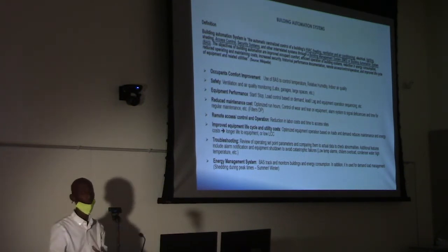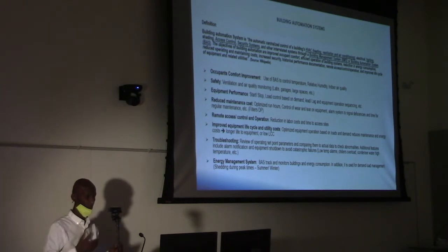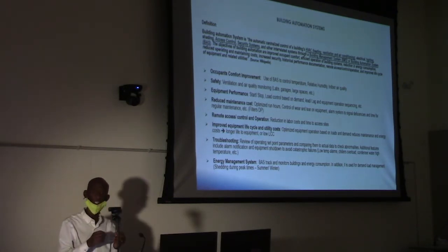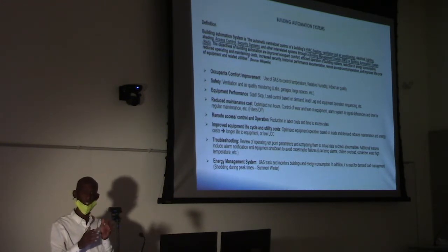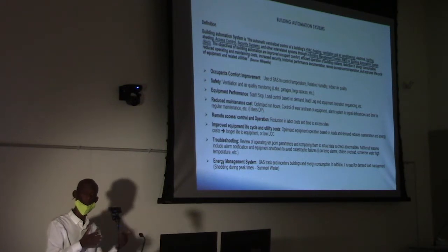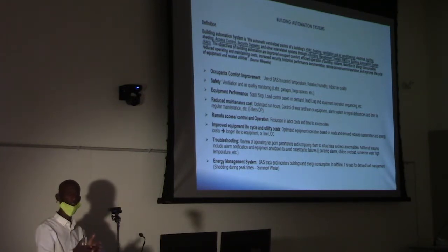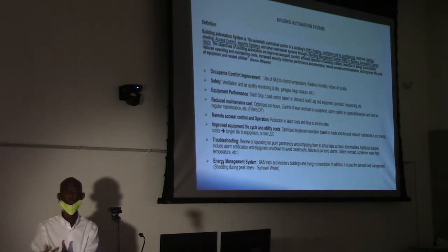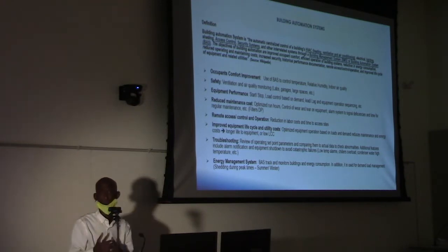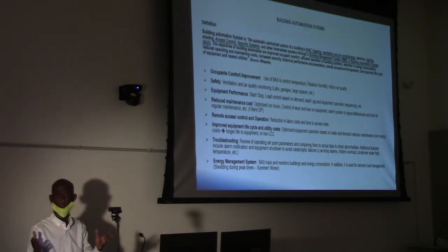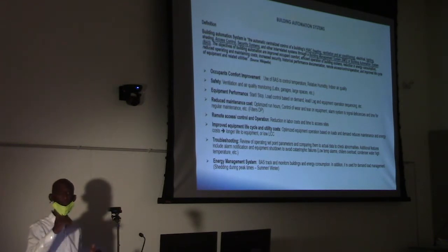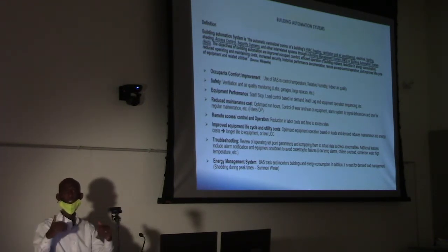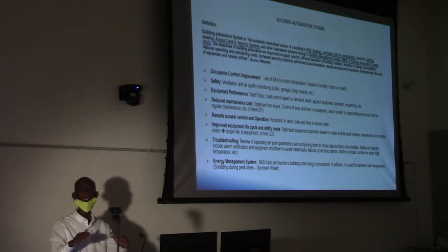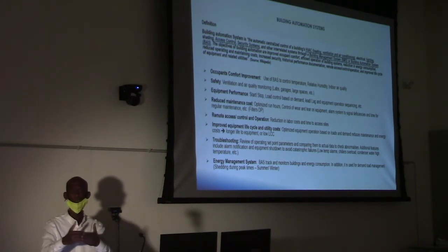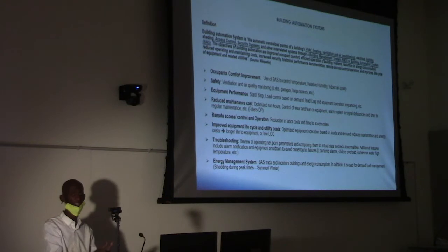So our building automation system has a feature that when there is a low temperature alarm, it sends notification to the system, and the system closes the dampers, prevents air from coming from outside, and then it blocks the airflow through the coil, and then the coil can survive. That's an example. If I take chillers, for instance, some chillers may be running with a high condenser water temperature. So what it does, it may damage the chiller. So when you have high condenser or hot water temperature coming back to the chiller, you may stop the chiller first and send an alarm. And the alarm will be just check the condenser water temperature. And the chiller won't start until you fix the problem.